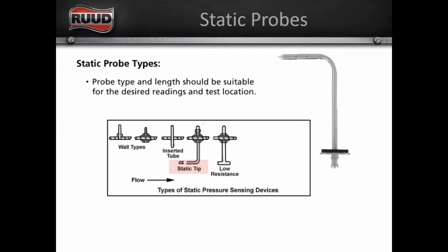If you just have a flexible piece of tubing and you stick it inside your ductwork, it is going to flex or flop down. And by doing that, depending on how it's oriented and where you are in the duct, you might not be measuring static pressure, you might be measuring velocity, or you might be measuring total pressure. So it makes your life a little bit easier if you've got some static probes.